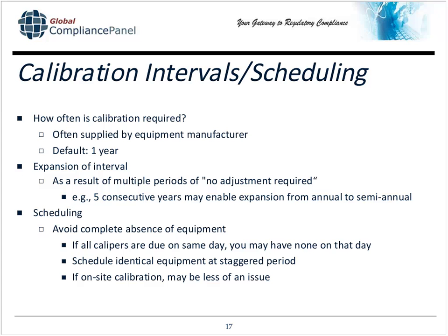If you have calipers, for example, very cheap pieces of equipment, you've got to calibrate them. They have to be in your calibration system. If you have all of them due on the same day, because it's much easier that way, that doesn't work, because on a particular day, you're not going to have any left. Stagger these things.